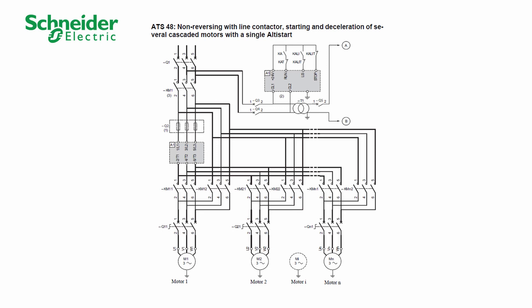When the motor M2 is at established regime, close KM22 and open KM21. The soft starter is now bypassed, open KA.